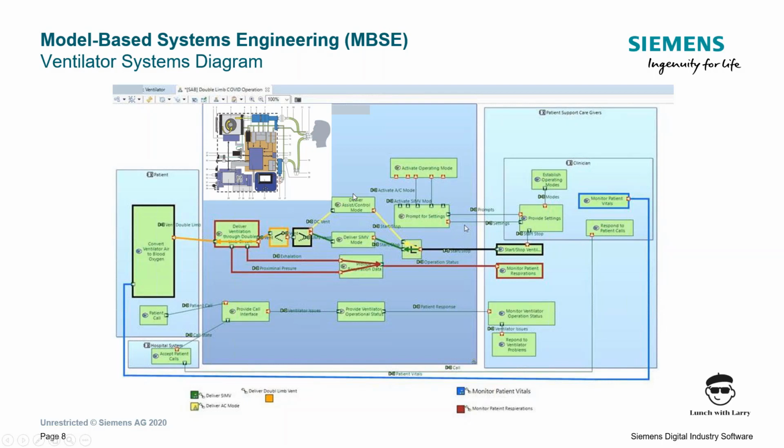It contains electrical components such as the power supply and a motor that would spin the air turbine. It also requires mechanical parts such as the fan to make sure that these electronics components do not overheat. The air and oxygen flows are regulated with valves and sensors, so we need to be able to make sure that those will be controlled appropriately. Then you have a microcontroller as well, which will allow to control oxygen and airflow levels.